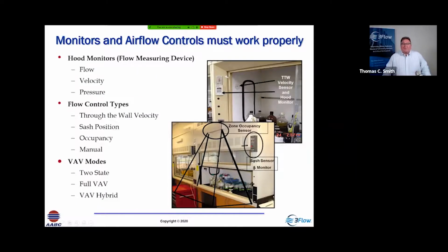We can look at different types of monitors: flow, velocity, and pressure. All fume hoods should have a monitor to alert the user to a low flow condition or an improper operating mode. Then we have different control types, as I mentioned: through the wall, sash position, occupancy. In some cases, we may even have manual, which should be discouraged. And then we have different operating modes: two-state control, full VAV, VAV hybrid. You could have a sash position controller that modulates flow based on sash position, coupled with a zone occupancy sensor. So now you have a different mode of operation. When someone walks away from the hood, it goes to a lower flow. Who challenges that? How do we make sure that flow actually modulates as we expect?